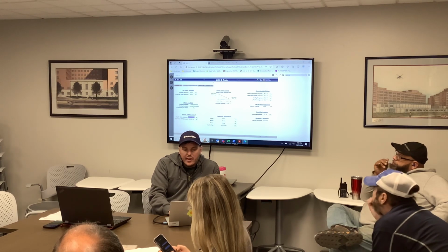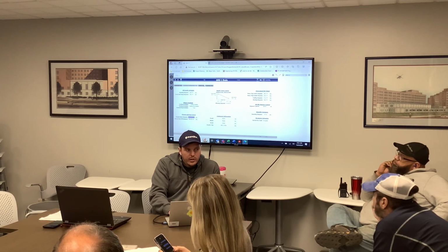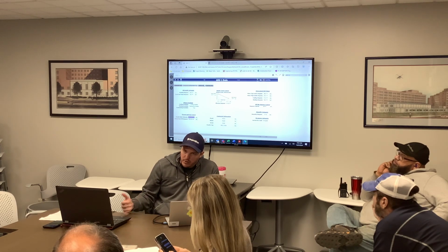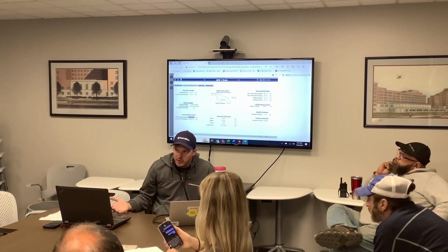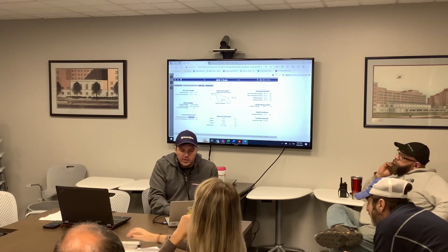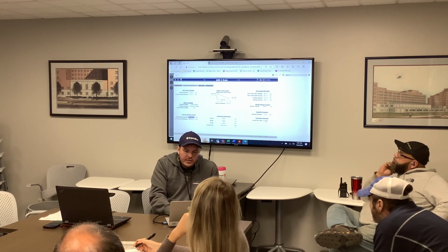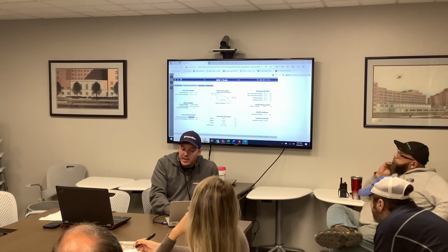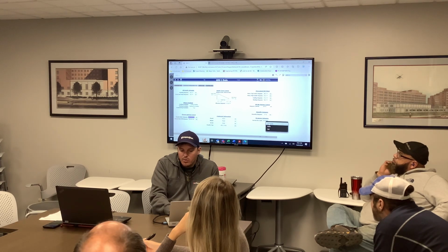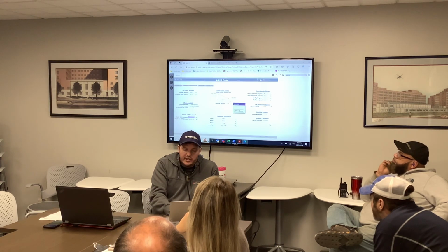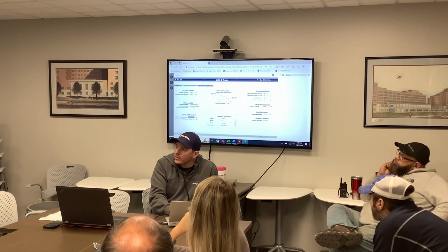Right now, I have your system set to occupied 24/7. I didn't see any schedules for the rest of your building, so I just assumed it's 24/7. But I will show you how to change that. This is the occupancy command it's getting from your schedule, and if you ever need to override this, you can just come here, right click it, and override it unoccupied.